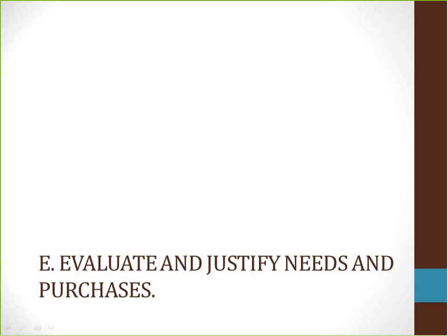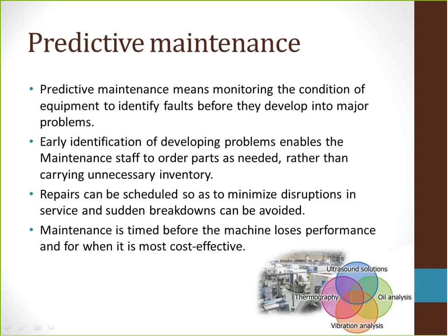Next, evaluating and justifying needs and purchases. Predictive maintenance means monitoring the condition of equipment to identify faults before they develop into major problems. Early identification of developing problems enables the maintenance staff to order parts as needed, rather than carrying unnecessary inventory. Repairs can be scheduled to minimize disruptions in service and sudden breakdowns can be avoided. Maintenance is timed before the machine loses performance and for when it is most cost-effective.